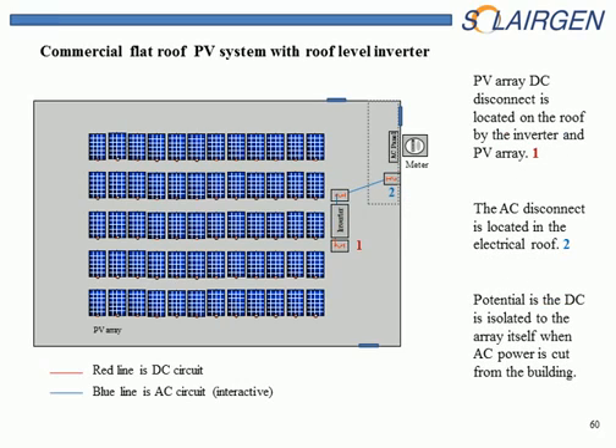In this case, this would be a later day, more modern, last few years PV system on a roof, where the inverters, I'm showing one inverter, but this would be probably multiple inverters on a roof, are located close to the PV array. So simply by disconnecting the power, you disconnect all the power up to the PV array. So just taking the meter out or disconnecting the main would do this. Chances of getting to an AC disconnect on the outside for the PV array is probably pretty slim. It's probably inside of the electrical room.